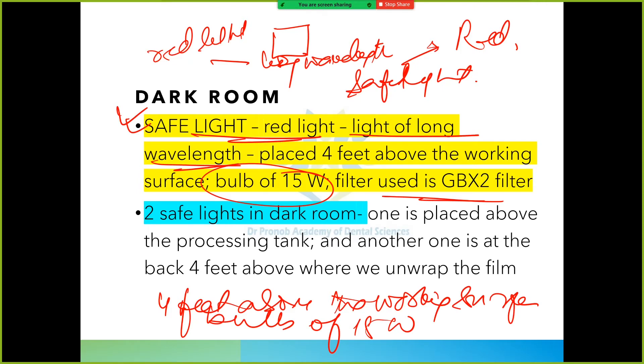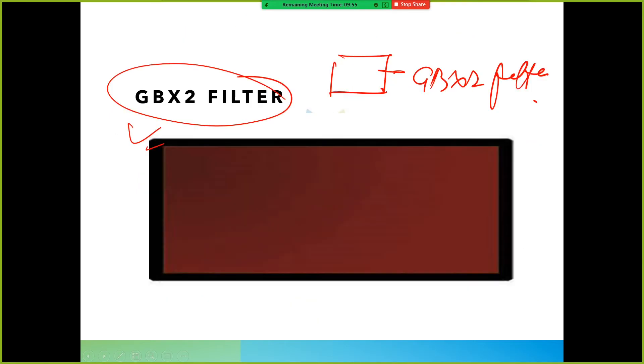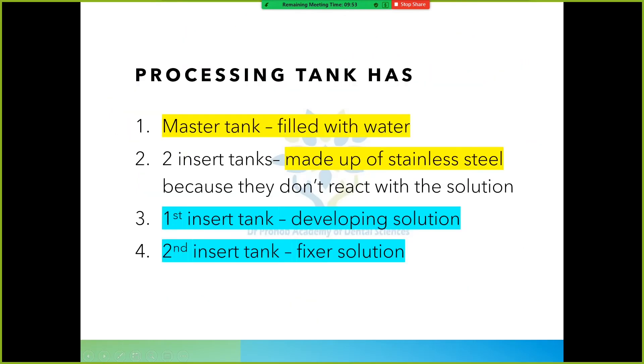There must be two safe lights in the darkroom. One is placed above the processing tank, and another one is at the back, four feet above where we unwrap the film. So there should be two safe lights - one above the processing tank and one above the film unwrapping area. The filter used is the GBX2 filter.